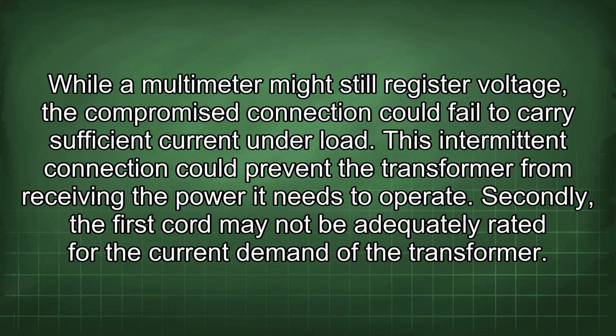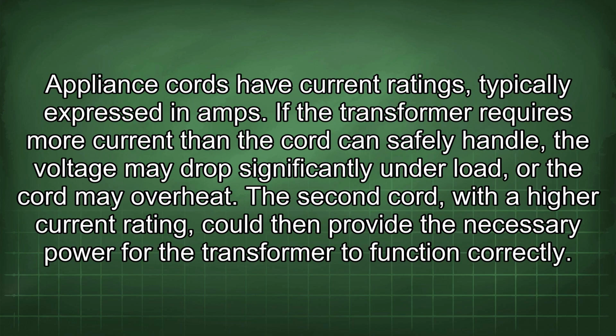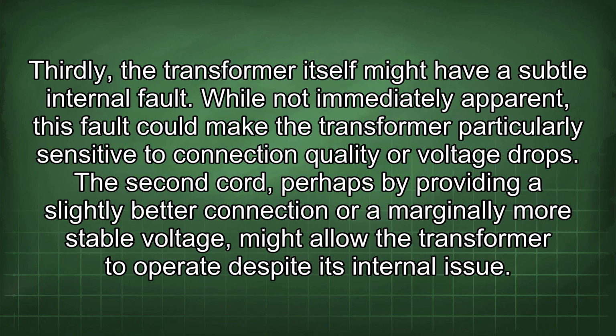Secondly, the first cord may not be adequately rated for the current demand of the transformer. Appliance cords have current ratings typically expressed in amps. If the transformer requires more current than the cord can safely handle, the voltage may drop significantly under load, or the cord may overheat. The second cord, with a higher current rating, could then provide the necessary power for the transformer to function correctly. Thirdly, the transformer itself might have a subtle internal fault.